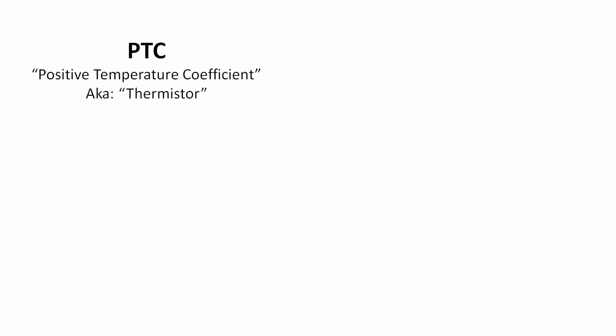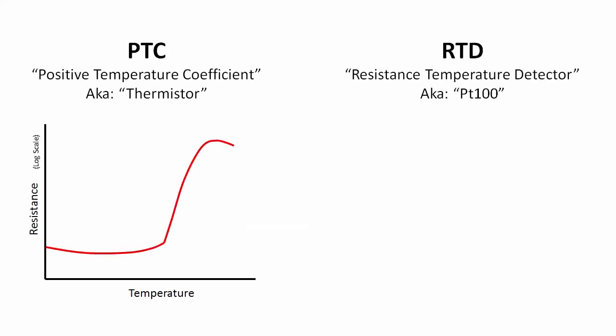The GS4 can use either PTCs or RTDs for temperature sensing. At a certain temperature, a PTC's resistance changes dramatically. When you buy one, you just pick one that changes at the temperature you want. The GS4 drive just looks for that rapid change to know when things have gone south.